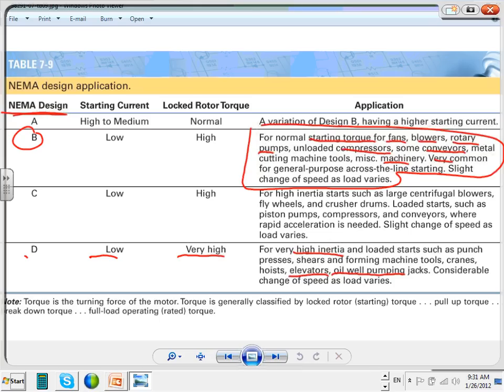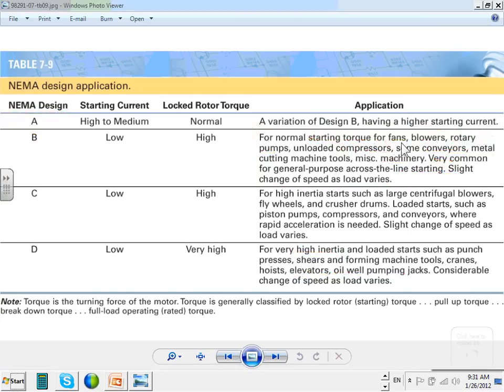While B is a fan. What's on a fan? To run a fan, what's the inertia on it? You know what I mean? So conveyors, you fill a conveyor with equipment and it stops. Now you're going to push a button and start. Imagine the inertia that you need to be able to pull these things together. So inertia or load, the ability to start, the starting torque, the ability to start things. So I want you guys to remember B, for whatever reason, the most common one.